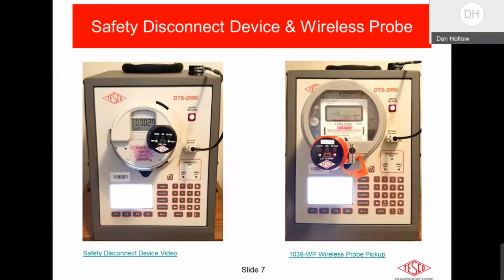Now, there are a lot of instances, for whatever reason, let's say you're using power line carrier communications. Your neighbor may have cranked up his arc welder, which is going to put out an enormous amount of harmonics. And now the adjacent house that has a meter with a service disconnect switch, and you're using power line carrier communications, they can't communicate with that meter. That PLC communications module is not a bad module. It's just being interfered with by an enormous amount of harmonics being put out by an arc welder or similar devices that can also introduce harmonics onto the fundamental waveform.